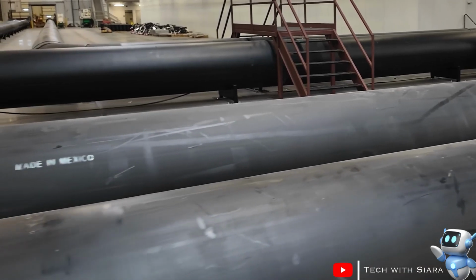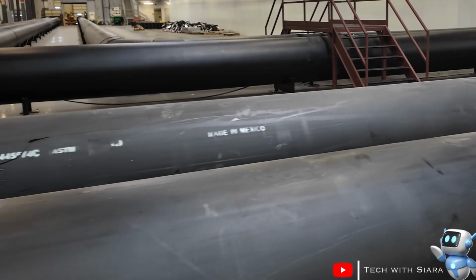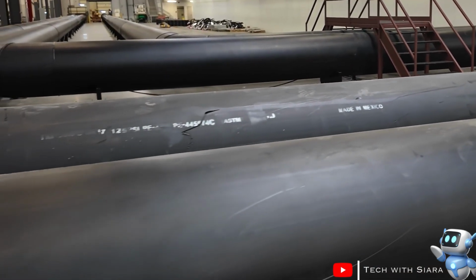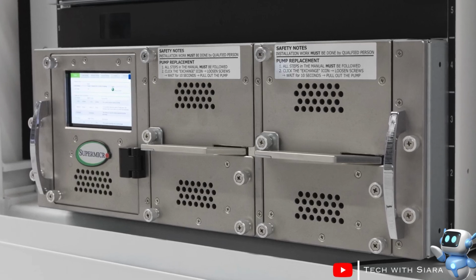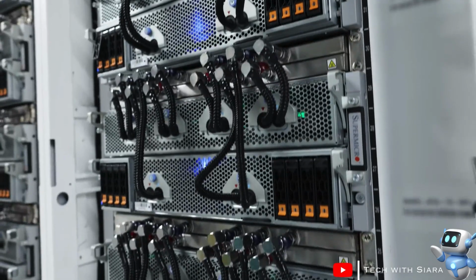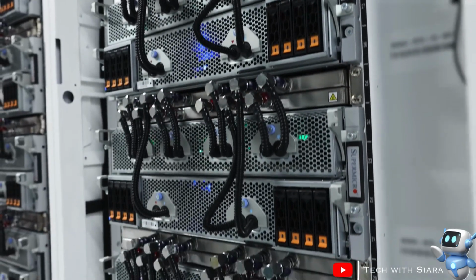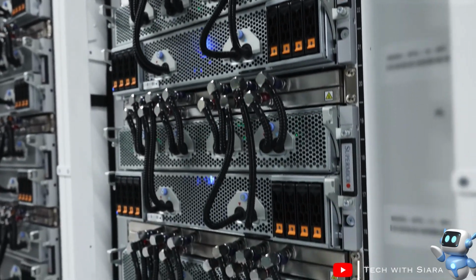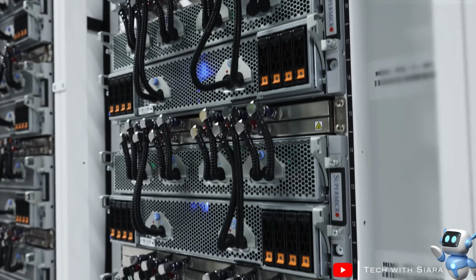Now let's go to the lower floor, where we have huge pipelines for hot and cold water. These pipes bring cold water from the cooler and supply it to the cooling distribution unit of each rack on the upper floor. They also take back the hot water from the cooling distribution unit and send it to the cooler. This is a great example of reusability.